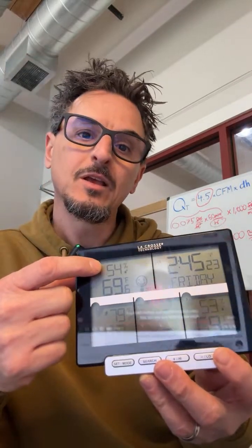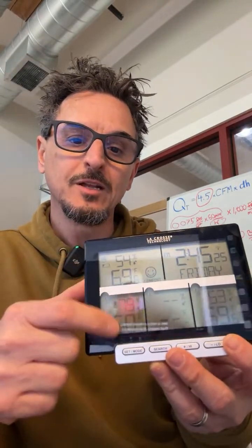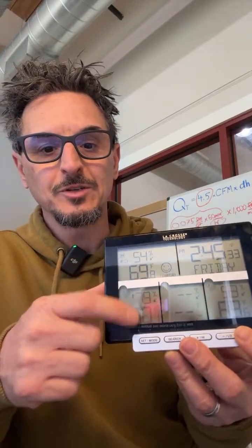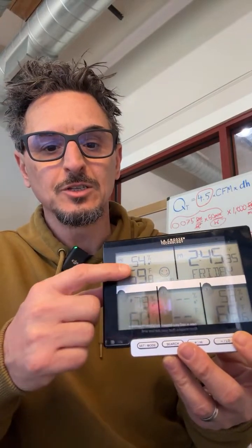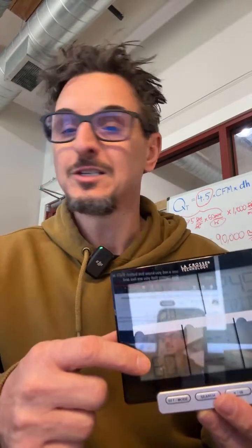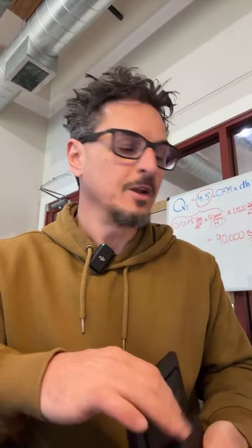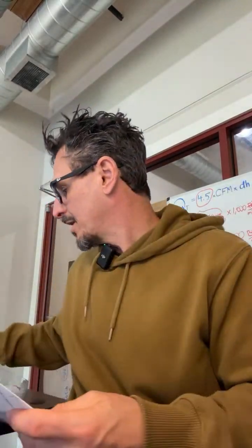So that's a good illustration of why relative humidity is not really a super good indicator of the amount of moisture in the air. It's relative to the temperature, right? So the dew point of these two conditions is very close, within a couple degrees. It feels nice in here. It's warm and dry, and it's cool and rainy outside. But the point is the relative humidity is not a great indicator of that. And if you've been around a while, you've definitely experienced that.